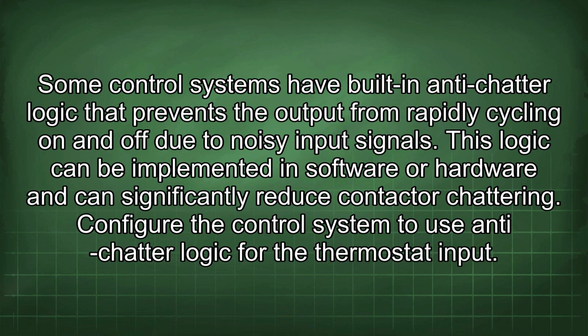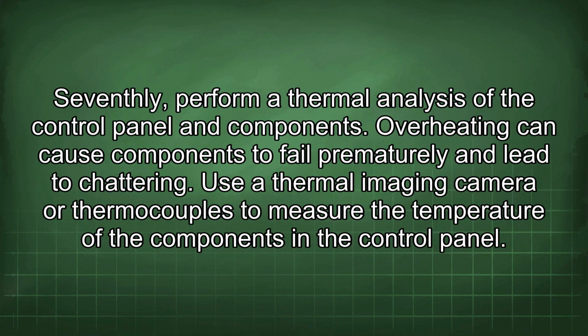This logic can be implemented in software or hardware and can significantly reduce contactor chattering. Configure the control system to use anti-chatter logic for the thermostat input. Seventhly, perform a thermal analysis of the control panel and components. Overheating can cause components to fail prematurely and lead to chattering.